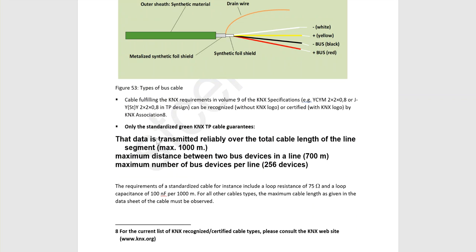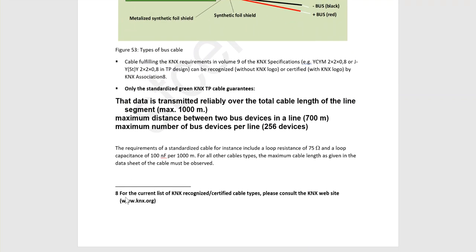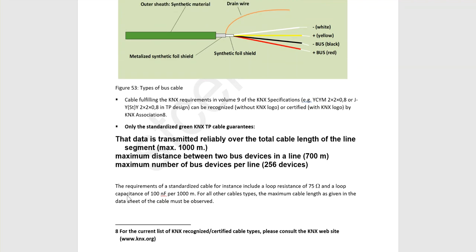So you should only use the standard cable to connect the KNX devices. We cannot use Cat5 or Cat6 or other network cable, of course. Here it also says we can use it for a 1000 meter line segment in KNX topology. The maximum distance between two devices in a KNX cable in one line segment is 700 meters, and we can use about 256 devices in one line. Also here the loop resistance is mentioned. Why do we need this information, like loop resistance and loop capacitance? Because when we want to check whether the cable is evaluated as the KNX standard for the cable, we should consider these 75 ohm and 100 nanofarad per 1000 meter.